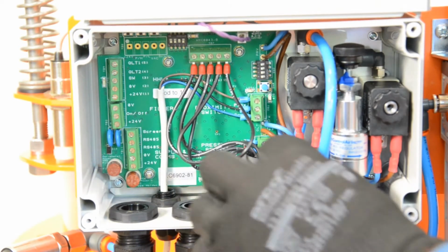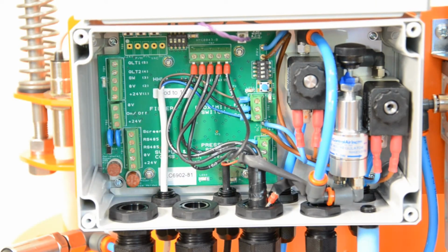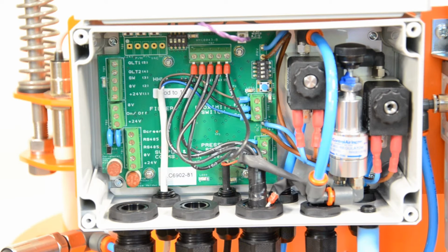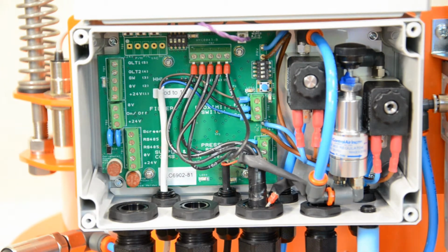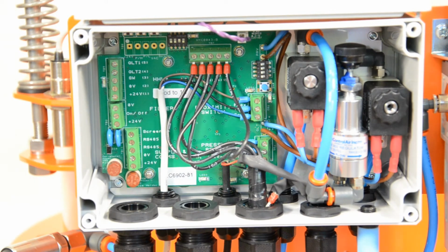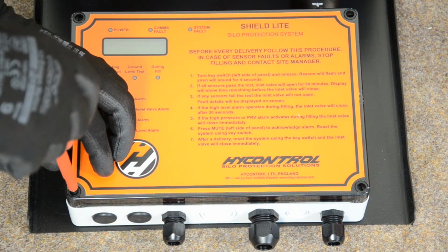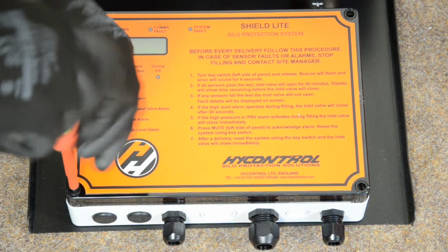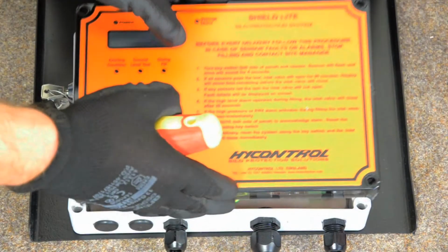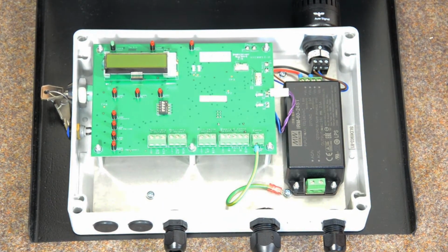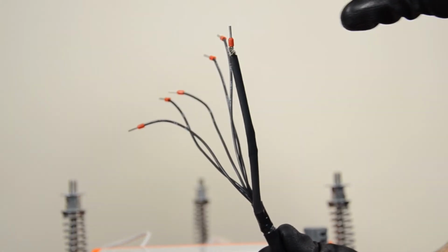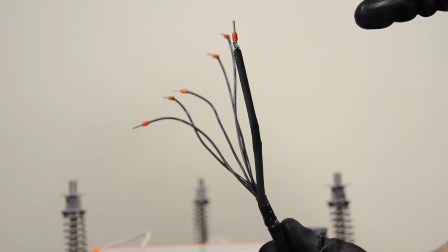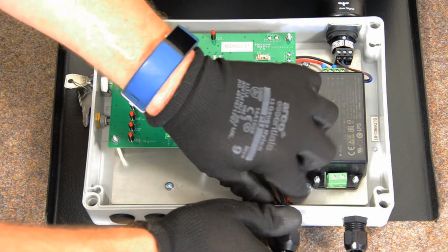The screen wire is no longer used, so it can be coiled up or cut off. This completes the wiring of the high-level switch. Now we will connect the control panel at the fill point to the silo top equipment. Remove the front cover from the panel. The panel connection uses a 5-core cable with a screen. Insert the cable through the larger port.